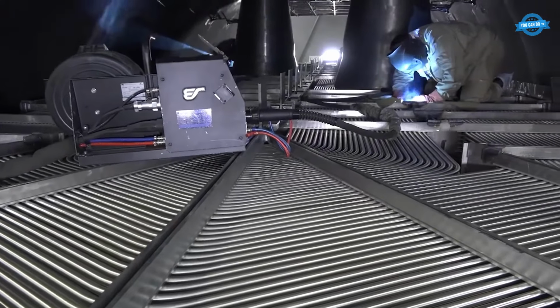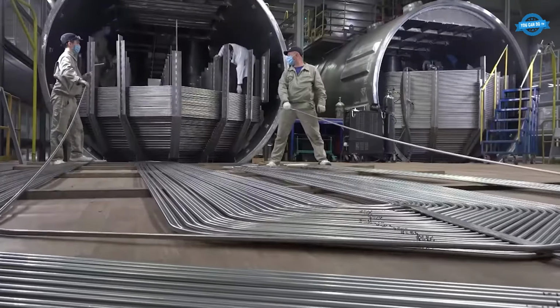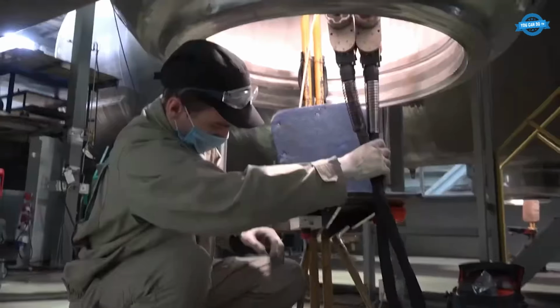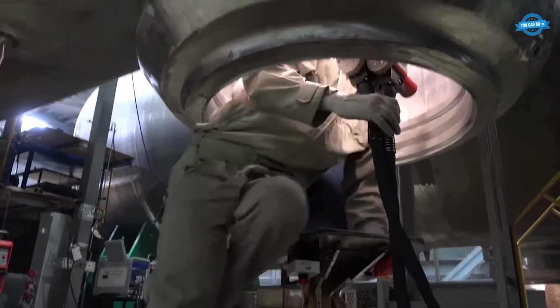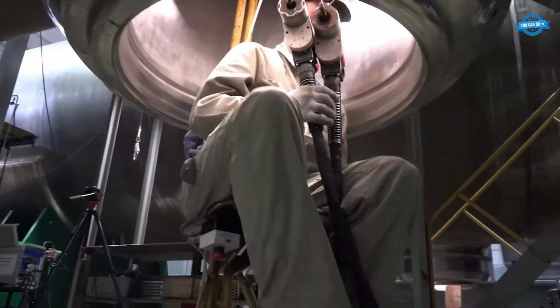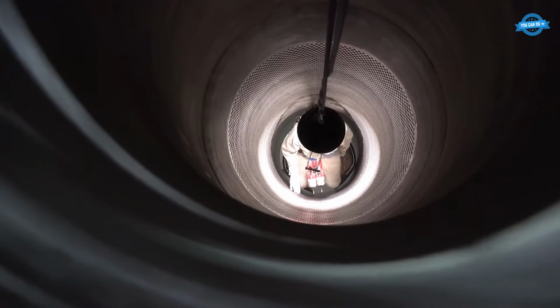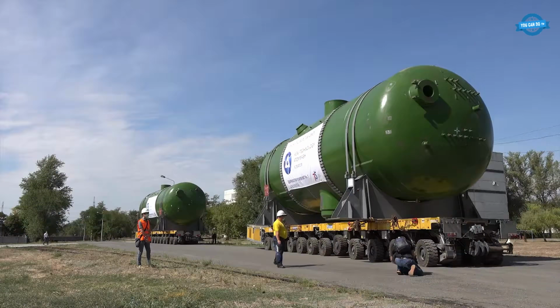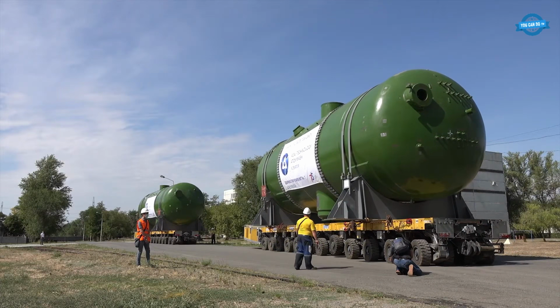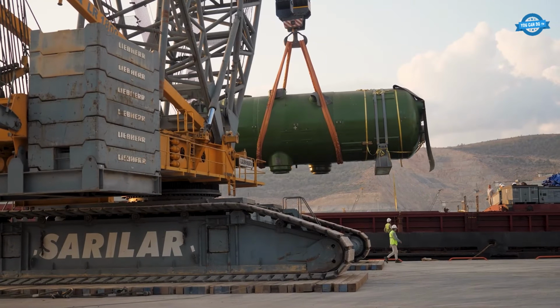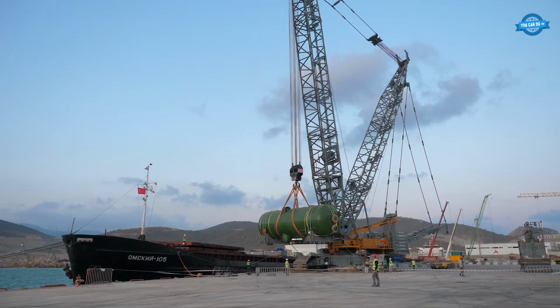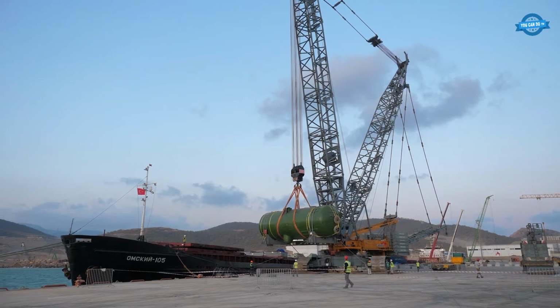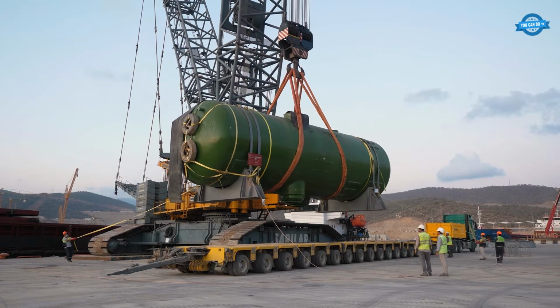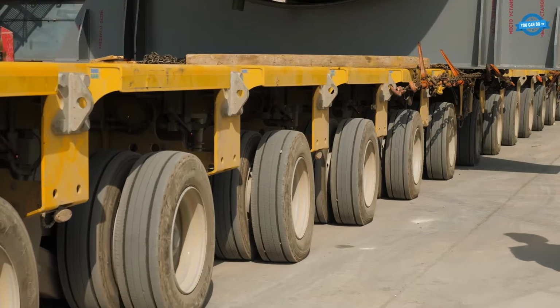One vessel isn't enough on its own. The reactor's heat has to become steam before it becomes electricity. Steam generators bridge that gap. 4 of them per unit, each around 365 tons, each a horizontal cylindrical vessel with elliptical heads. Inside sits a bundle of tubes carrying primary loop coolant at high pressure, while feed water flashes to steam around the outside.